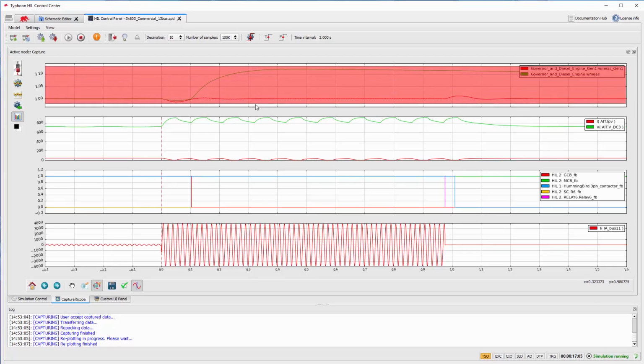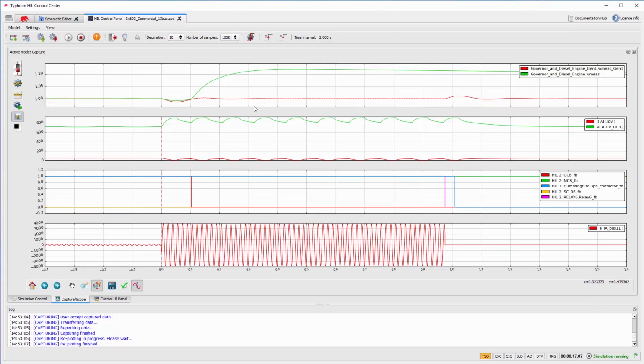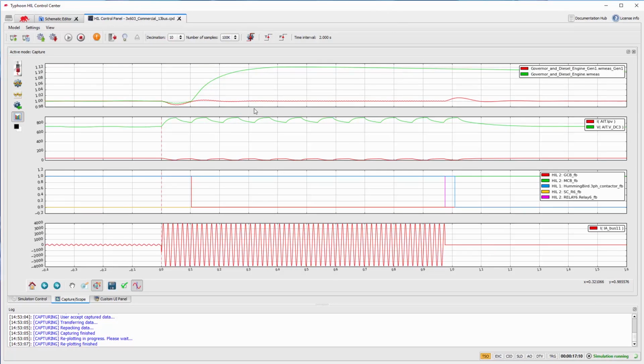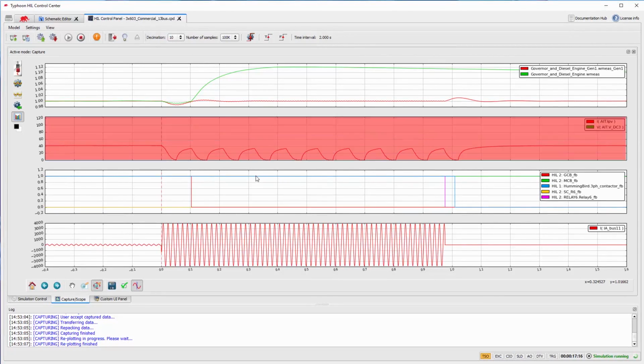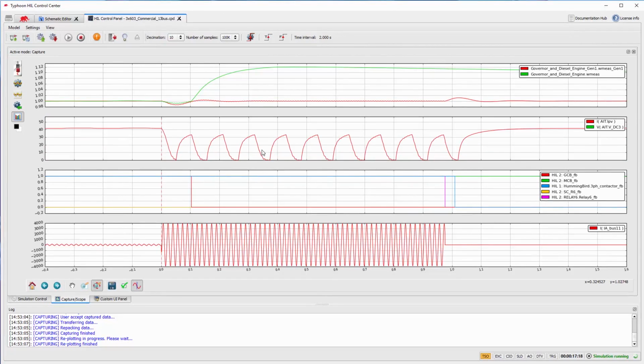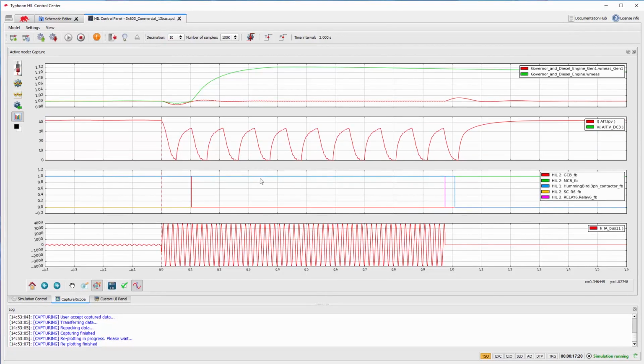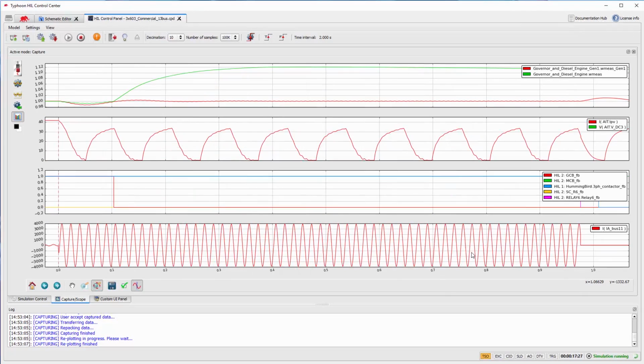Genset 1 supplied power to the short circuit, but had oscillations in speed that also had a higher order harmonic disturbance. Genset 2 disconnected in about 0.11 seconds because of high voltage at its terminal. The Hummingbird disconnected from the grid right after the fault was cleared by the Relay 6. The reason for it disconnecting is the same as in the previous cases studied, DC link over voltage.